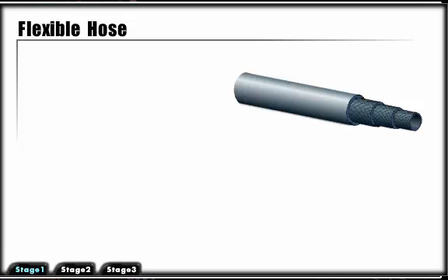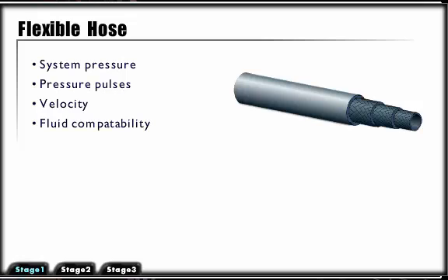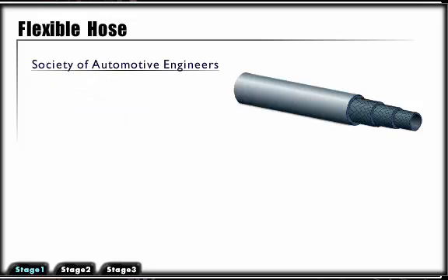Hydraulic hoses are used in applications where lines must flex or bend. In considering the use of hoses, one must first look at system pressure, pressure pulses, velocity, fluid compatibility, and environmental conditions. Hose construction has been standardized by the Society of Automotive Engineers.